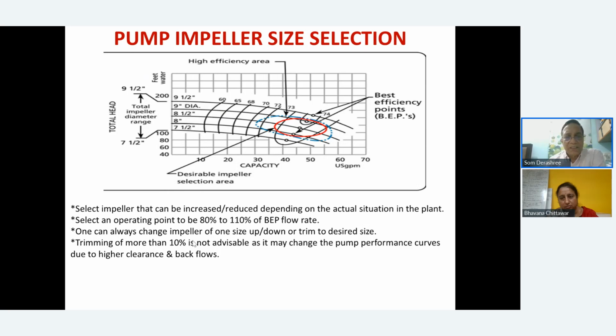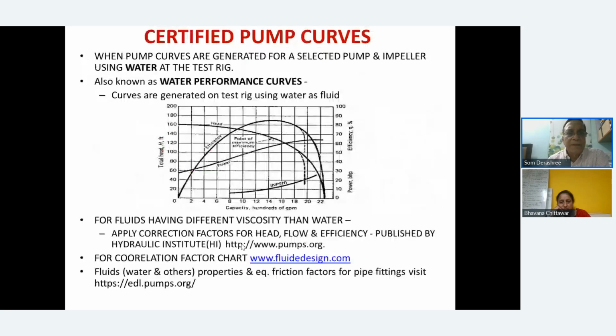One can always change the impeller one size up or down and trim to the desired size. We already discussed that, and trimming more than 10% is not advisable. Why? Because then the gaps might increase, the performance curve might change, and a lot of backflow might start, or the pump characteristic curve itself may change. So it is not advisable to trim a pump by more than 10%.